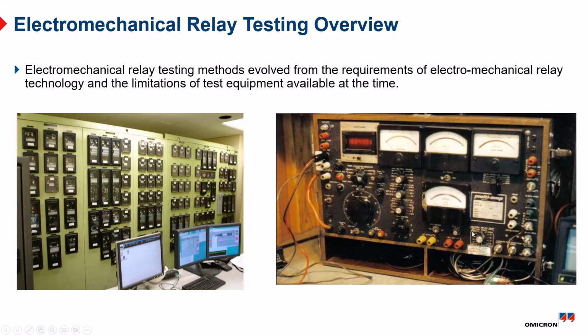On the right, this is an SR51 multi-amp, one of the first purpose-built protective relay test sets, kind of around 1950s or so. This one actually had an upgraded digital display, so that would put this one in use somewhere around the mid-70s when the LED timers came in. Before that, they had an analog electromechanical stopwatch that measured the trip time. So you can see that the testing was a bit more complex, but the testing itself really grew out of the requirements of commissioning electromechanical relays, and also the capabilities of the relay test equipment that was available at that time.